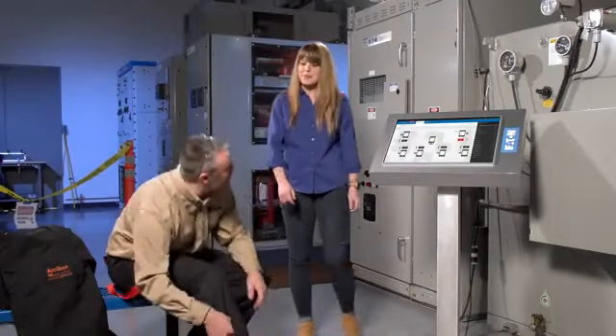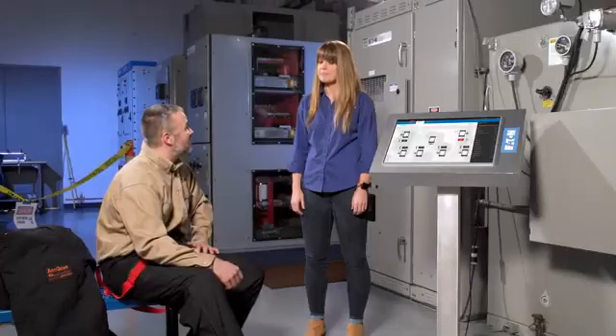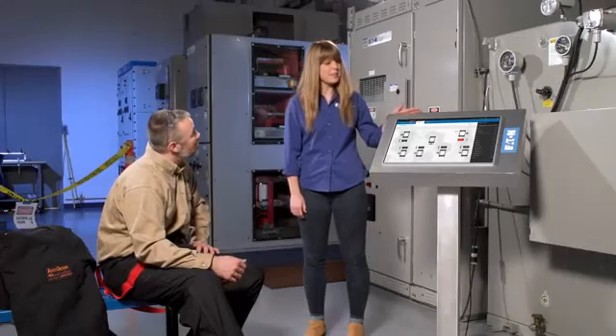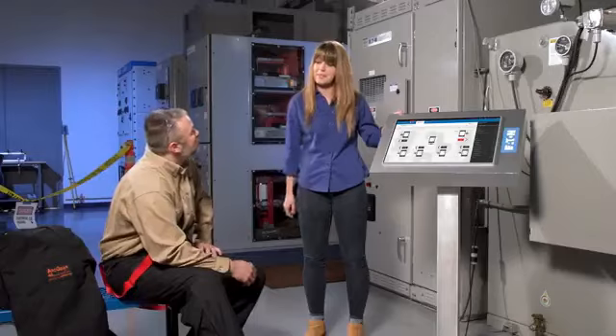Eric, why are you putting your 40 cal suit on? The customer wants to see me rack out that medium voltage breaker, and it's got a 30 cal arc flash label on it. Well, why don't you show them the other options for racking that breaker out? I guess I should. I could show them the integral racking or the remote power racking device. Actually, I was thinking we could show them this Power Expert dashboard and we could rack it out from here.